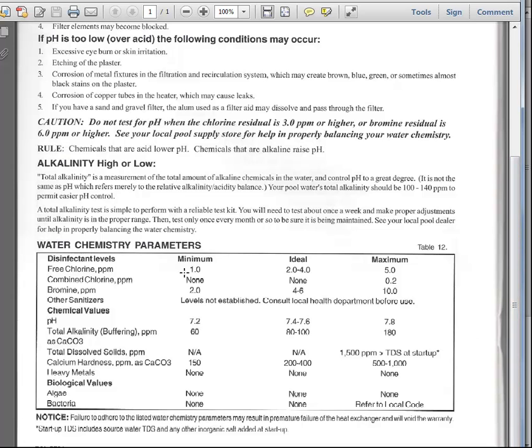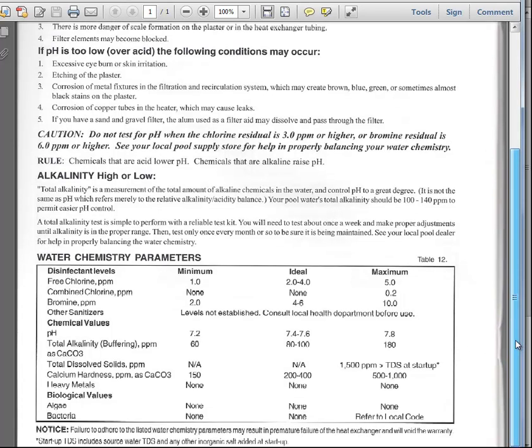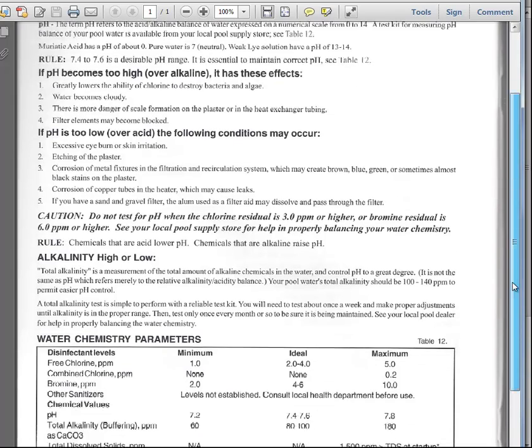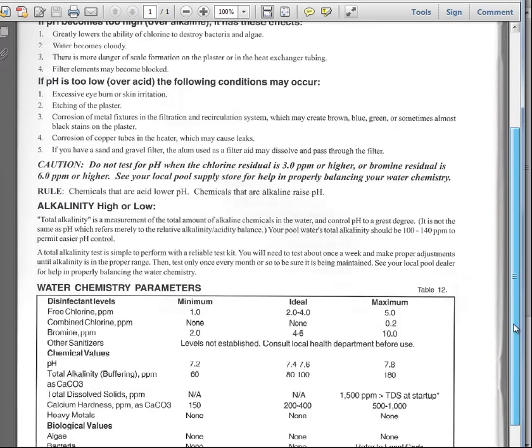These are your standards on pool chemistry, okay? Just not pH, okay? Everybody thinks it's just pH. It's not, all right? If you're out of balance, it will void your warranty. Got a leaky heat exchanger and it's 6 months old or a year and a half old, guess what? I can prove very easily it's pool chemistry just by pulling off the header and seeing the copper looking gone. So I can prove it's pool chemistry. And I can very easily prove that it's not over. If you add too much water too quickly, over 120 gallons a minute, I can prove that you're not pushing 120 gallons a minute.